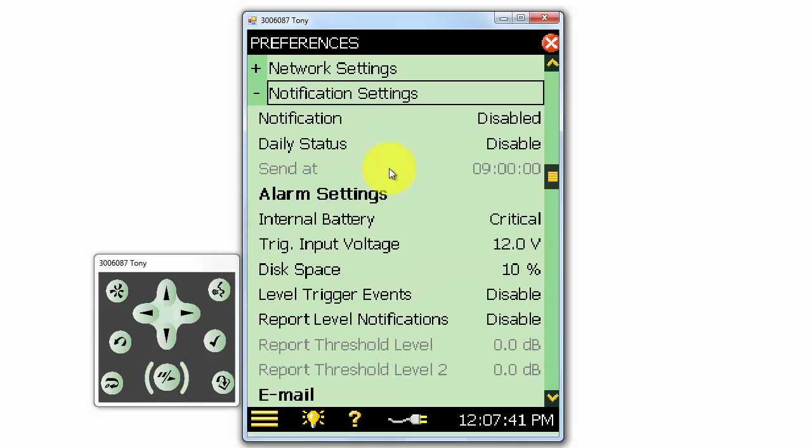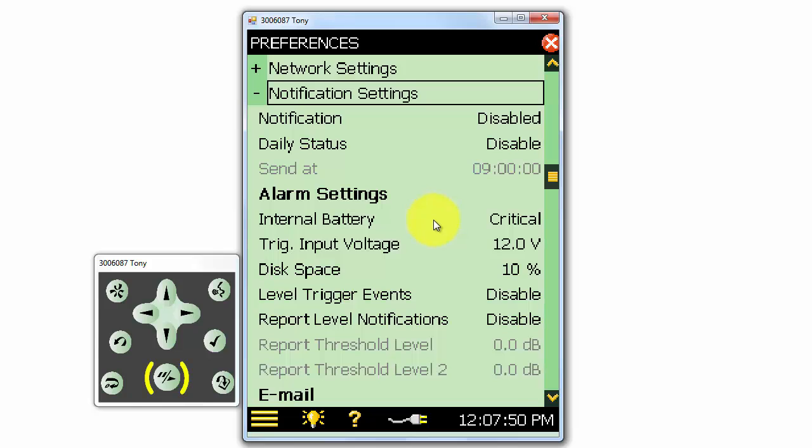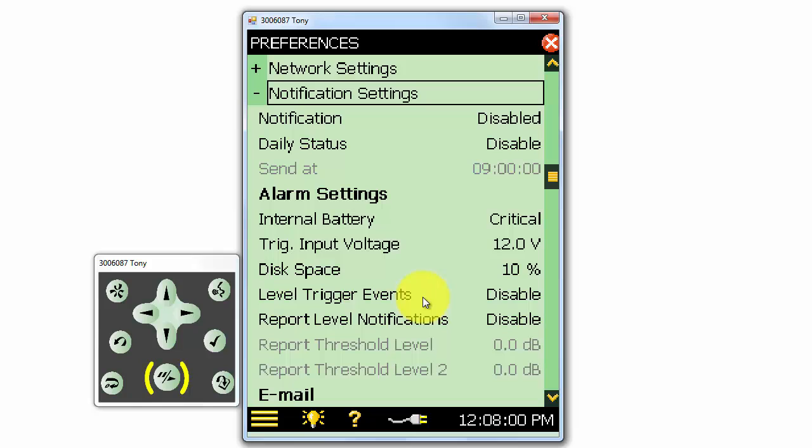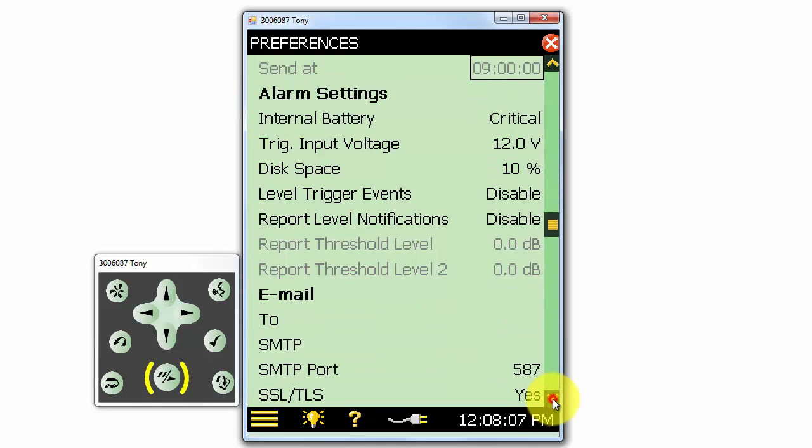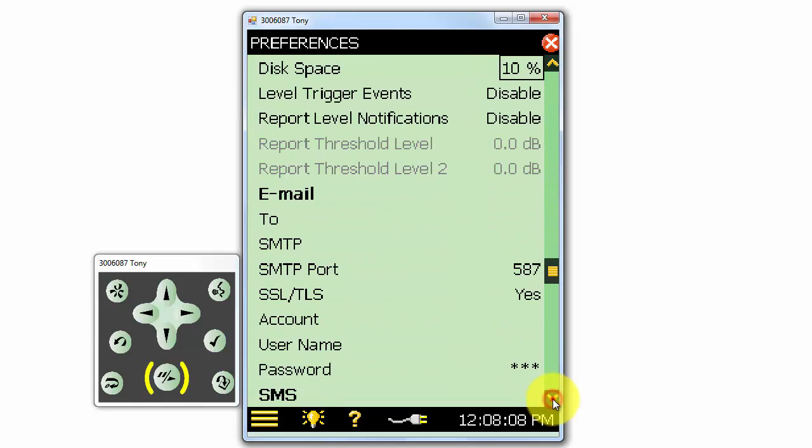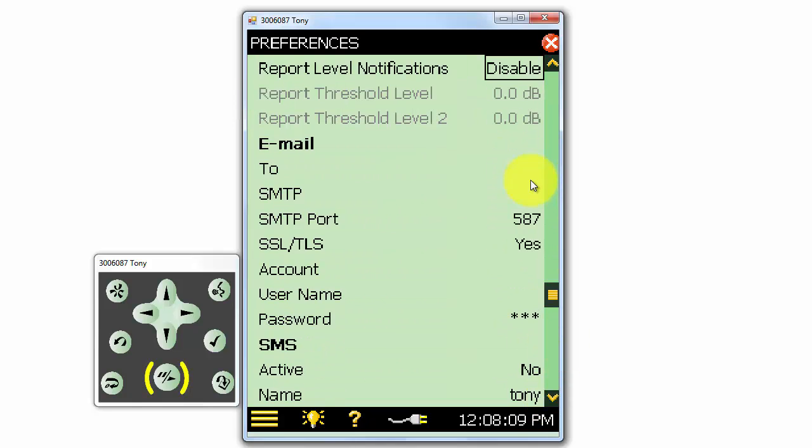If we're connected to a network, we can have the meter send out notifications, such as the daily status of the meter, if the meter battery has reached a critically low level, if the meter is running out of disk space, or if a specific sound level has been exceeded. These notifications can be very useful for remote monitoring applications. We can send out these alerts via email or SMS message.